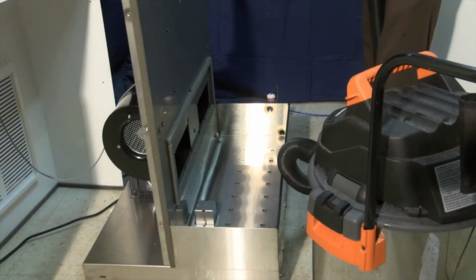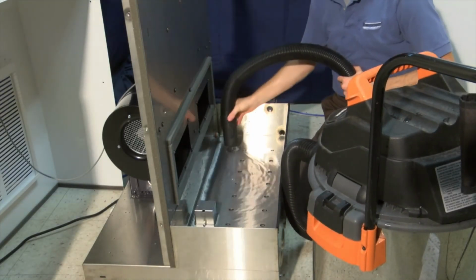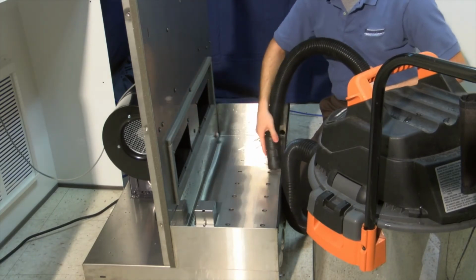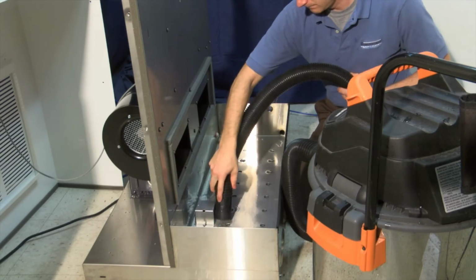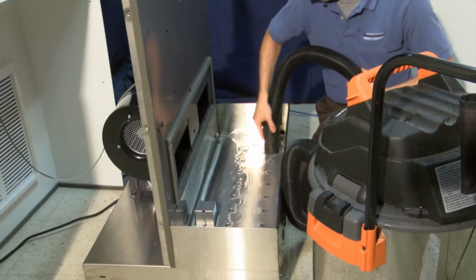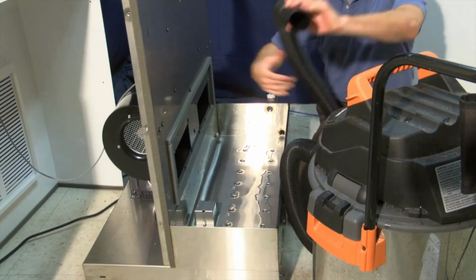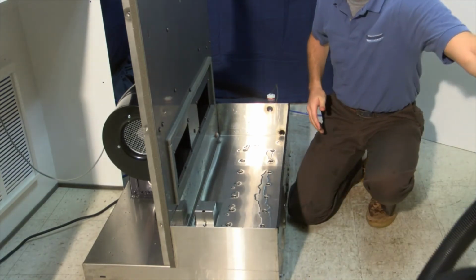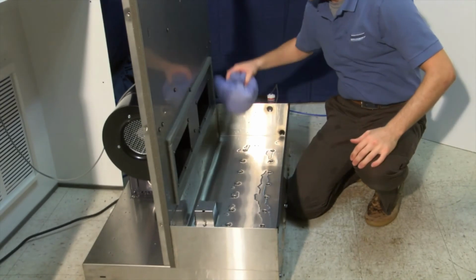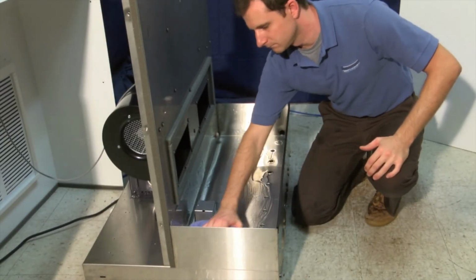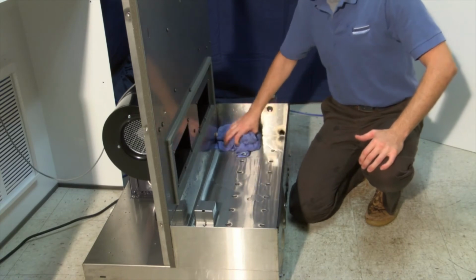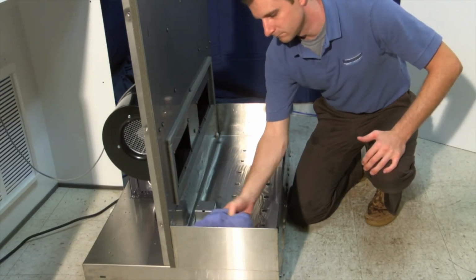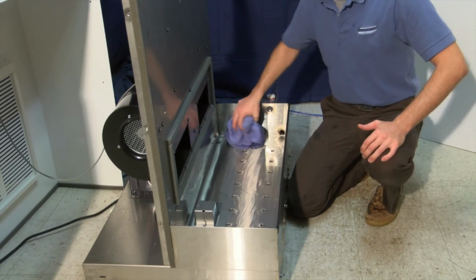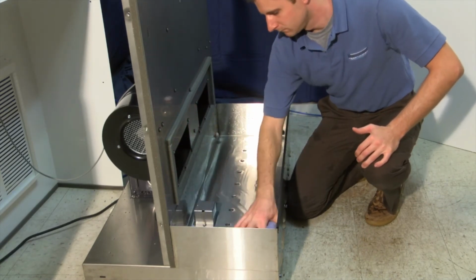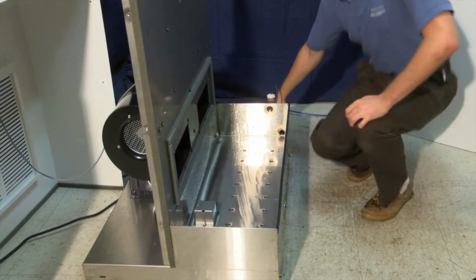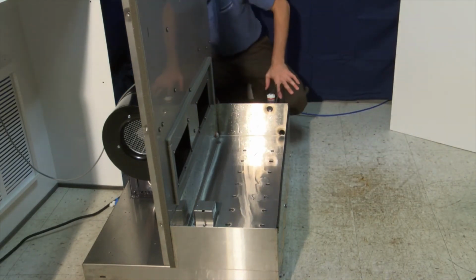Some applications may find they need to clean the inside of the unit to keep the water pan clean and clear. To do this, simply shop vac the water out of the water pan. Use a diluted alcohol or bleach solution and wipe the inside of the water pan out. Do not use a chemical cleaner, as the finishing agents and chemical cleaners can harm the crystallized transducers. You simply want to disinfect the water pan. You also do not want to scratch or scrape the transducers themselves. You can let the bleach or alcohol solution set on them for a short time and flush them out with fresh water.